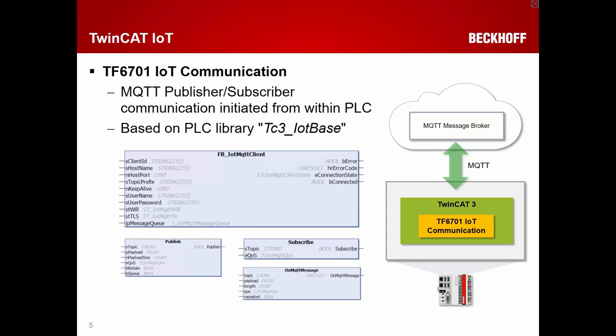Different function blocks are available that enable you to establish connectivity with an MQTT message broker, which can sit in the public cloud, in the local network, or even on an industrial PC. You can use security mechanisms like TLS, username and password, and certificates to encrypt your communication channel. After connecting to the broker, you can publish data structures, single variables, or arrays, and also subscribe to receive data.